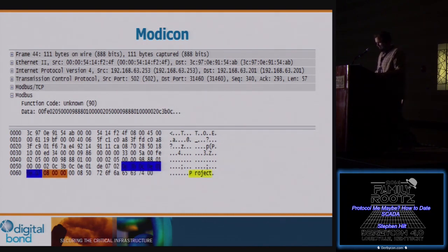Let me skip through the transitions there. So the version, at that time, was 008, which is stored in Little Endian there at the bottom. The project name is highlighted as well. And then the date timestamp is actually fairly interesting. It's also in Little Endian. 07DE is 2014. 01, it was January when it was last configured.